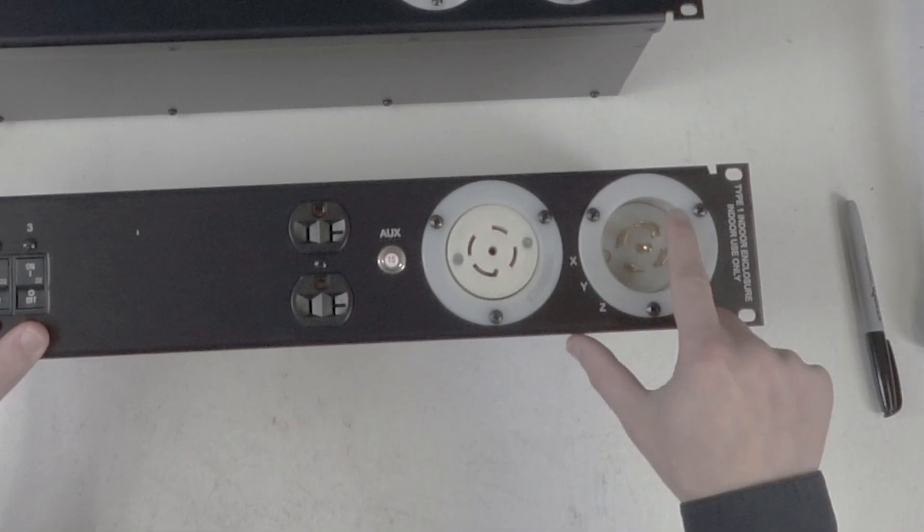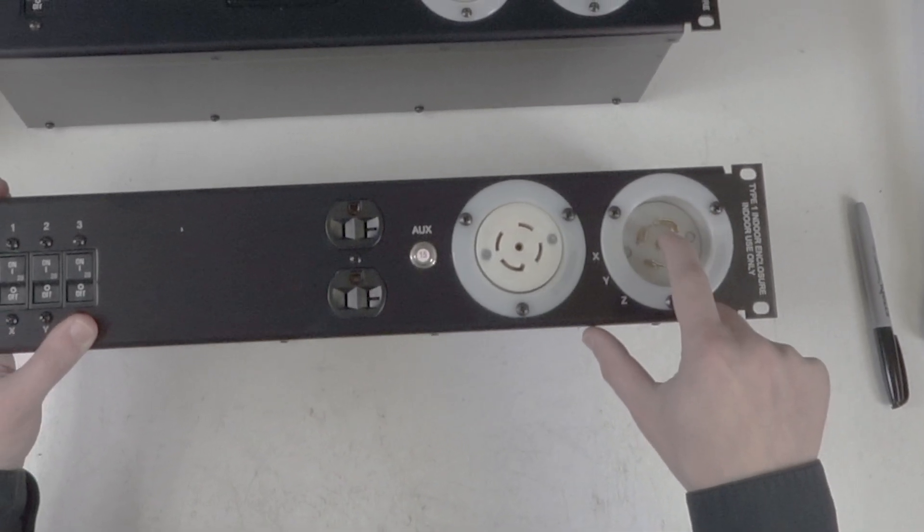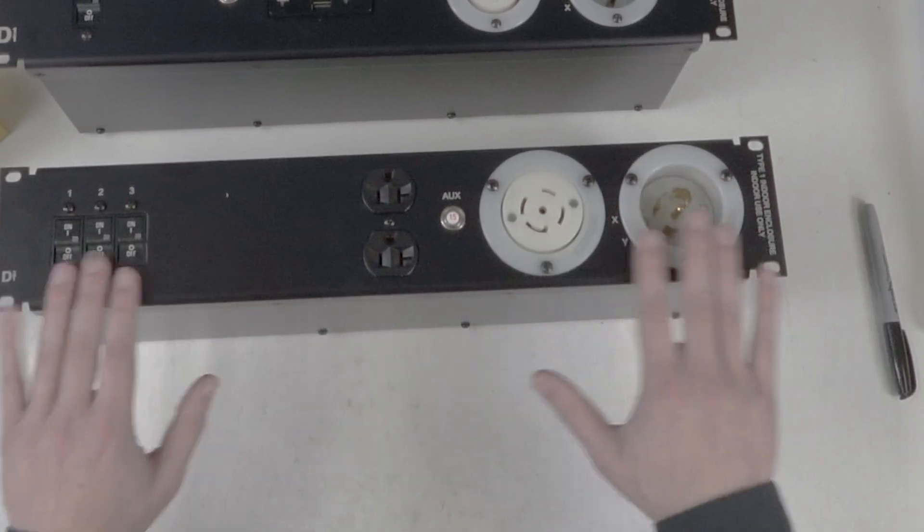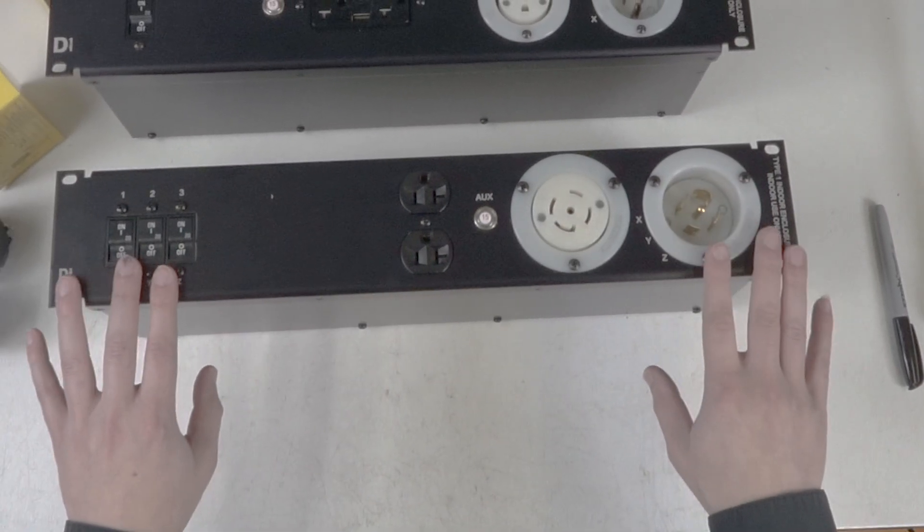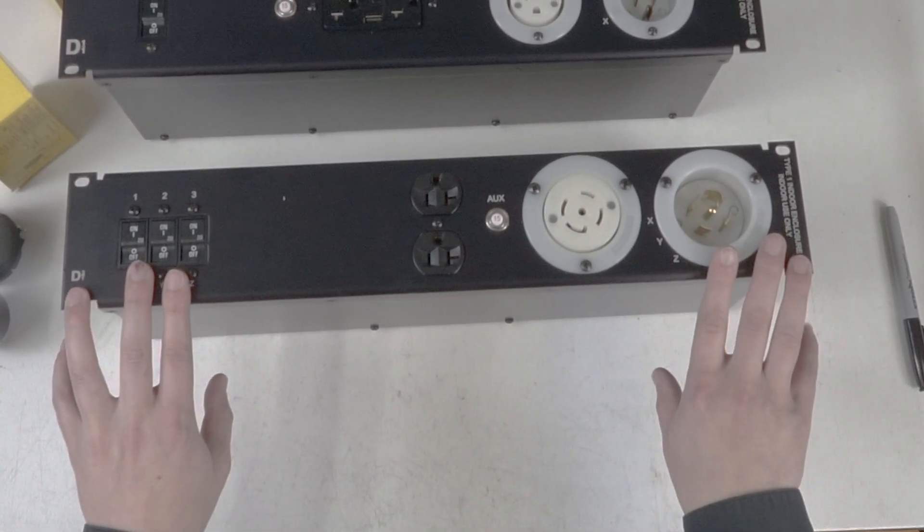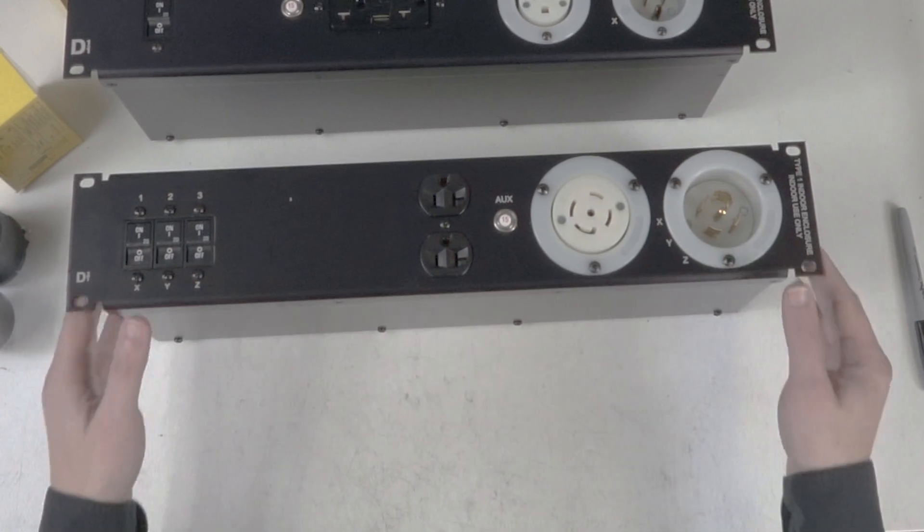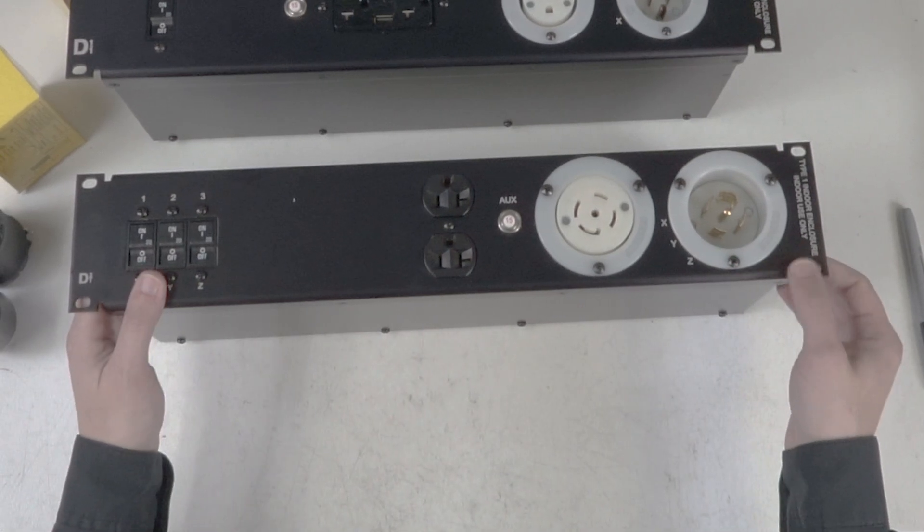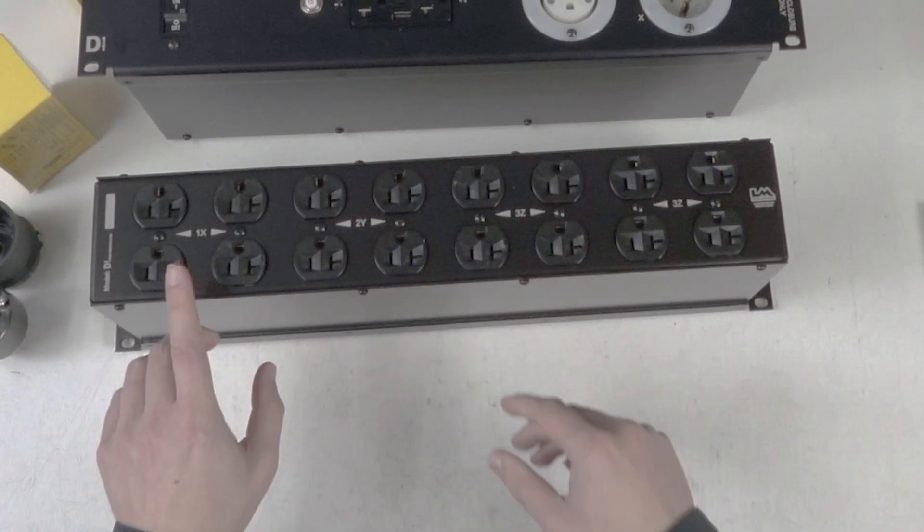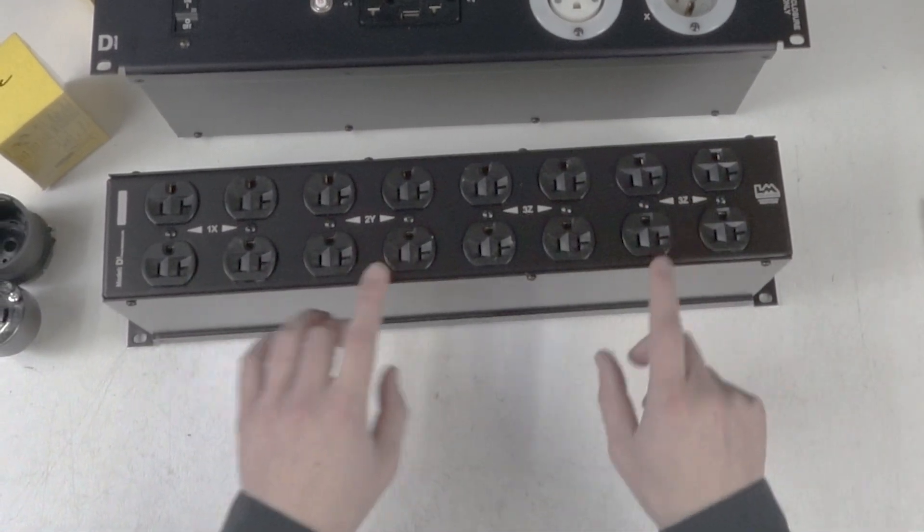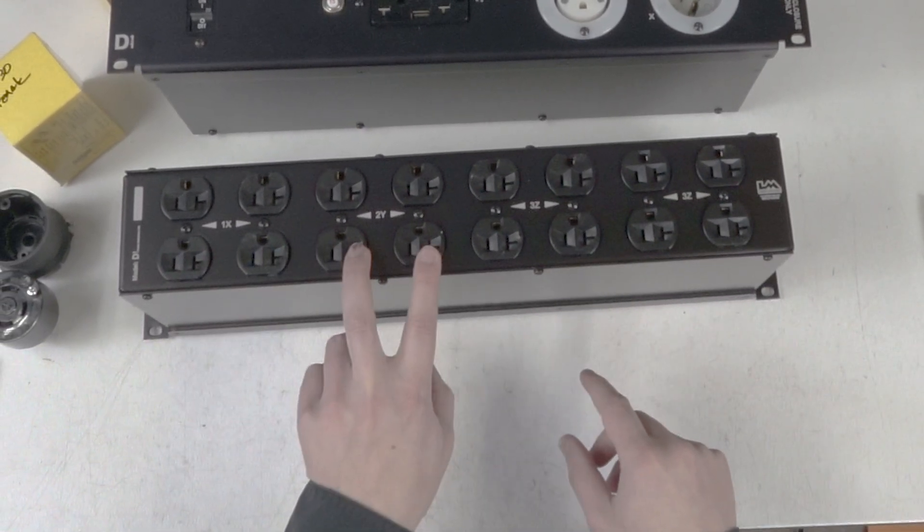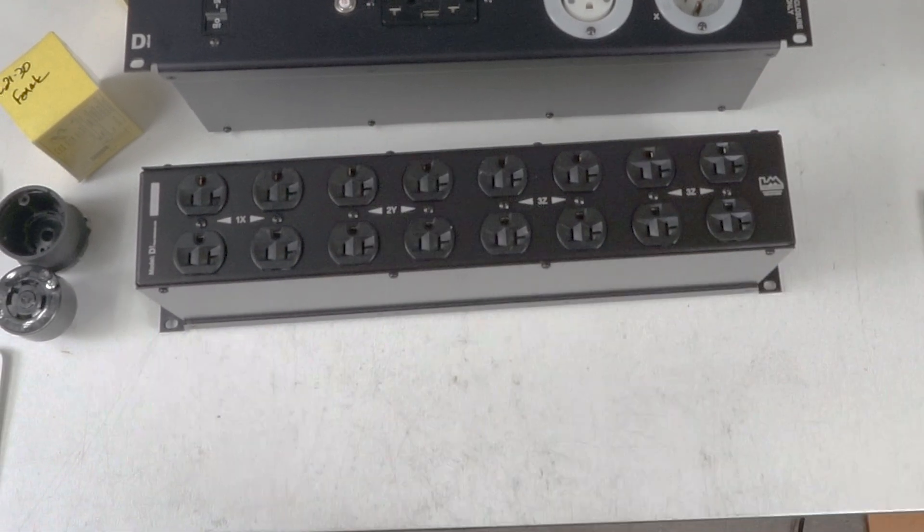In the entertainment world, we use what's called a three phase Y configuration, meaning it's a five wire configuration: three hots, a neutral, and a ground. We split that up into legs of X, Y, and Z. So this is a breaker, this is a breaker, this is a breaker.